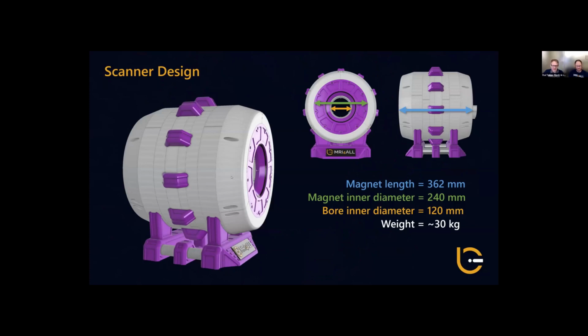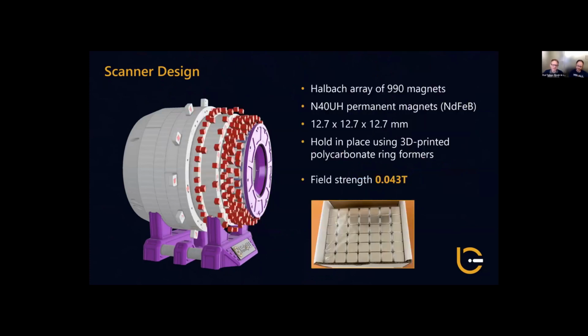Now, if we remove these outer plastic parts here and look inside the scanner, you can see that the magnetic field of the scanner is created by a Halbach array. So this Halbach array is created by 990 permanent magnets, which are indicated here in this red color. And we used N40UH permanent magnets for this. And these magnets are about half an inch long, or like cubed, so around 13 millimeters. And here in this photograph, you can see how these magnets look like. This is how they were shipped. And these N40UH magnets were specifically chosen because they are a little bit more resistant toward demagnetization.